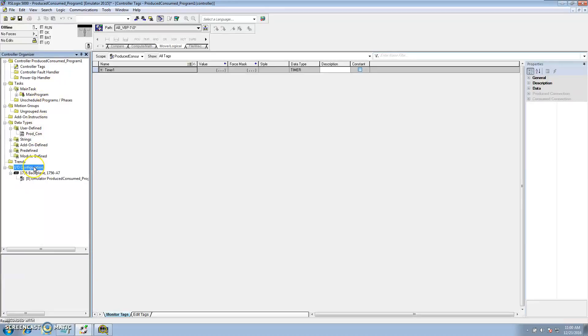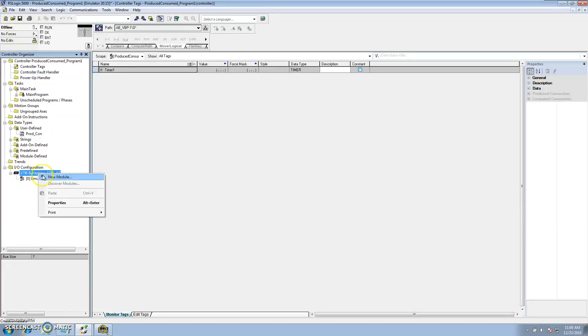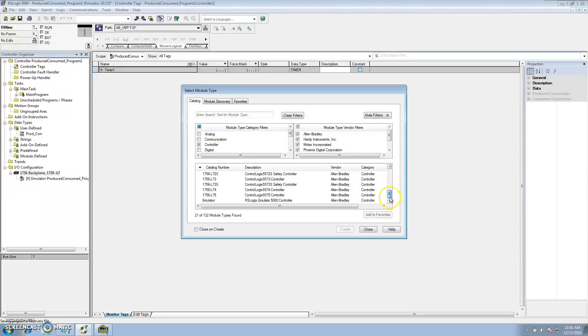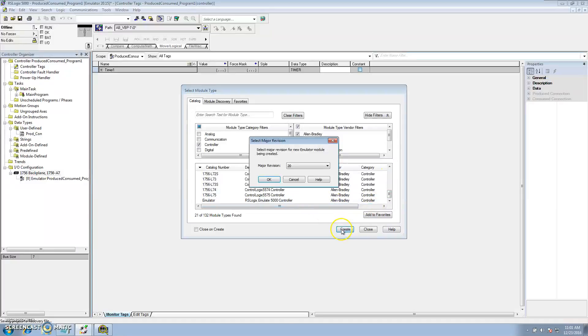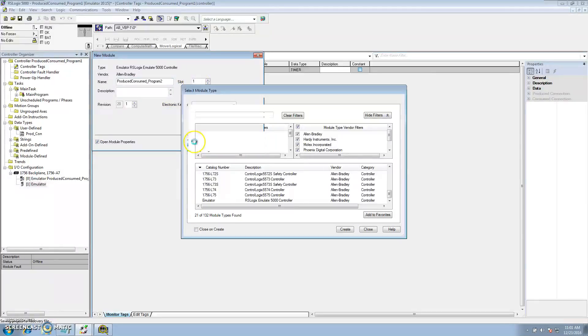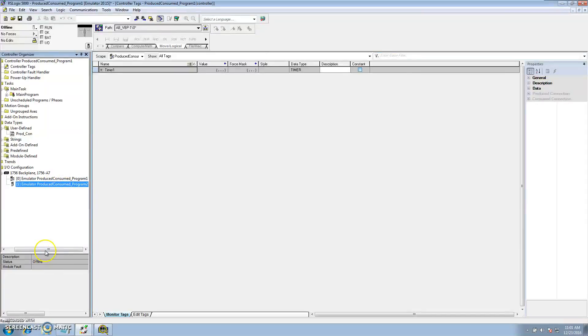First, you want to make sure you go to your IO Configuration, go to the backplane, and add in the other processor. Right-click, select module, go to Controller. Since we're using the emulator, I'll use the emulator processor. I'm on version 20. I want to name it the same as the program I'm talking to, which is Produce Consume Program Two, and it's going to be in slot one because Program One is in slot zero.